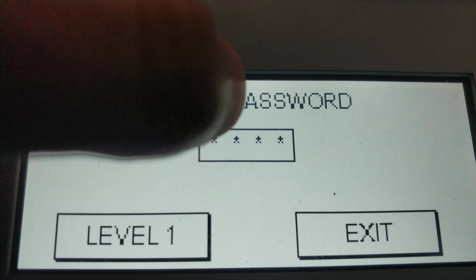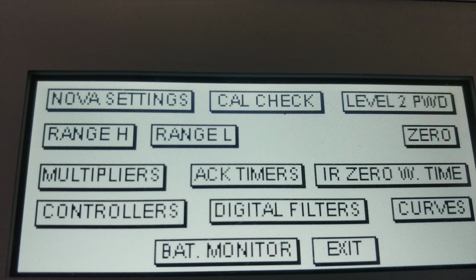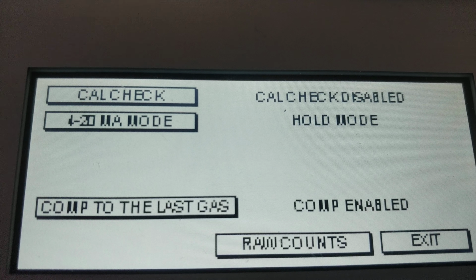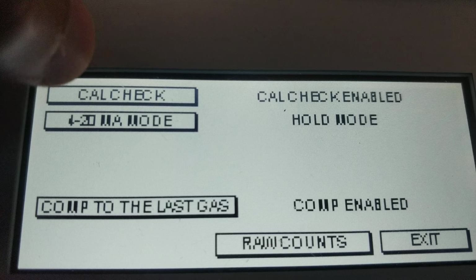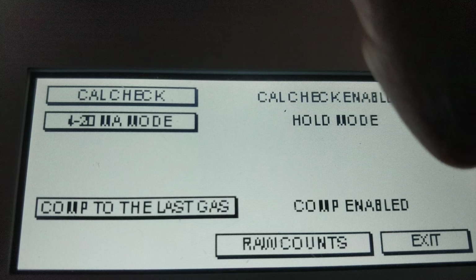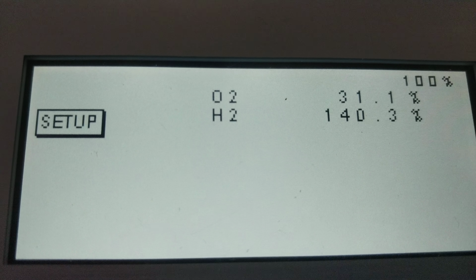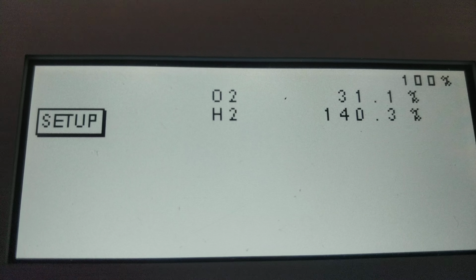Setup, so we go level 1 password to level 1. 270 is the password again. Enter level 1. Okay, Nova settings, and then we want to re-enable the CalCheck. So set the CalCheck to enabled, and then exit, and then we should be good to go. And that should fix the problem that you're having. And that's it.